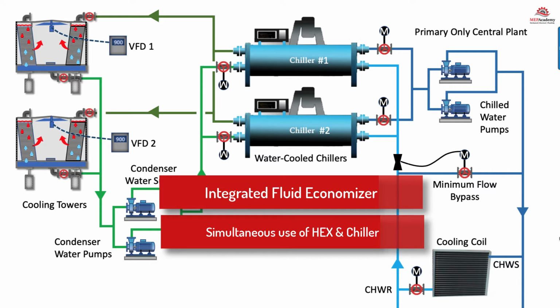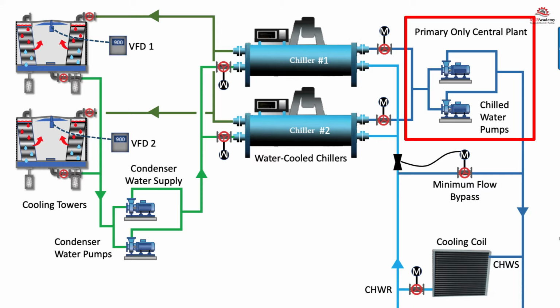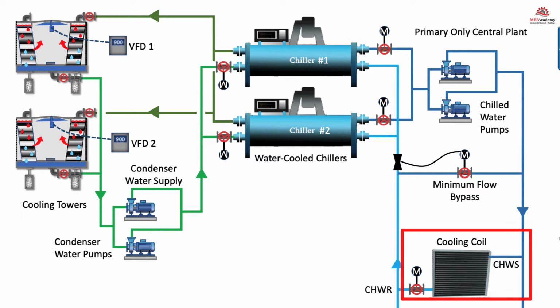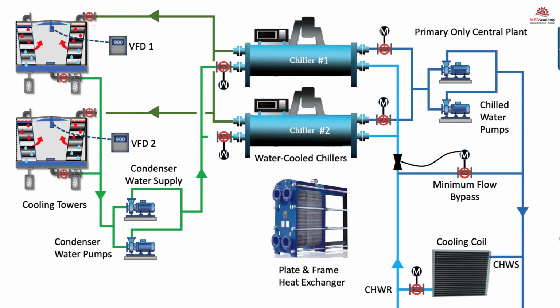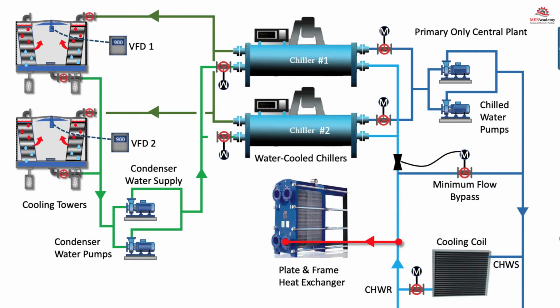This is a typical primary only chilled water central plant layout where the primary chilled water pumps serve the chillers and the building load, represented here as a cooling coil. A plate and frame heat exchanger will need to be added in series with the chillers on the chilled water side for the transfer of thermal energy between the condenser water and chilled water sides. For an explanation of how plate and frame heat exchangers work, see our previous video. We will tap into the chilled water return piping and connect to the heat exchanger to pre-cool the chilled water return before sending it onto the chiller.